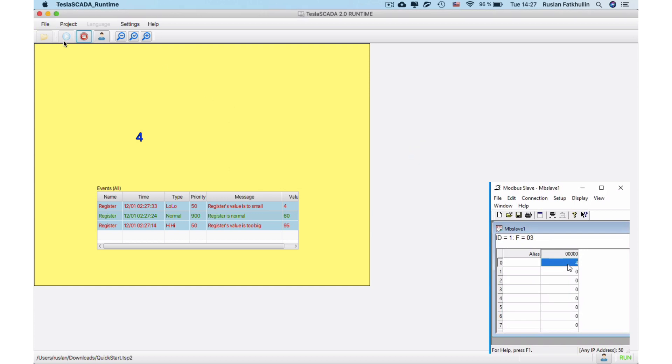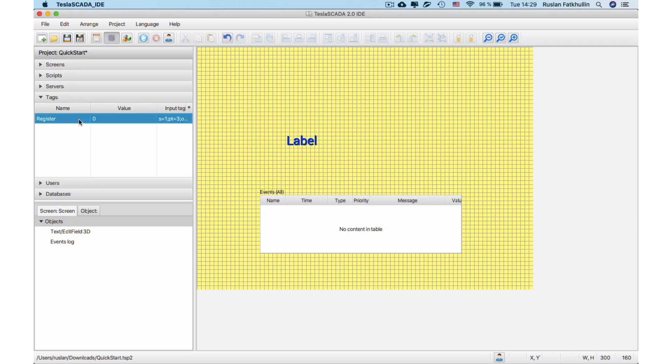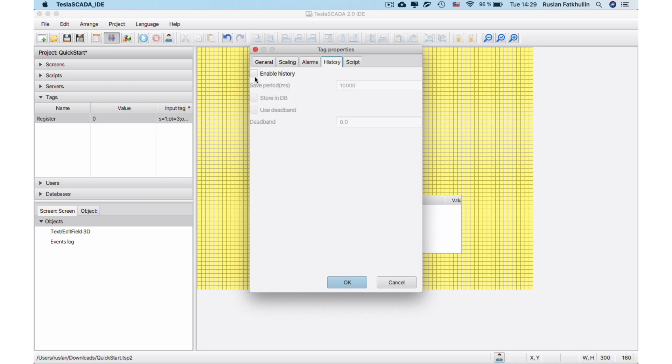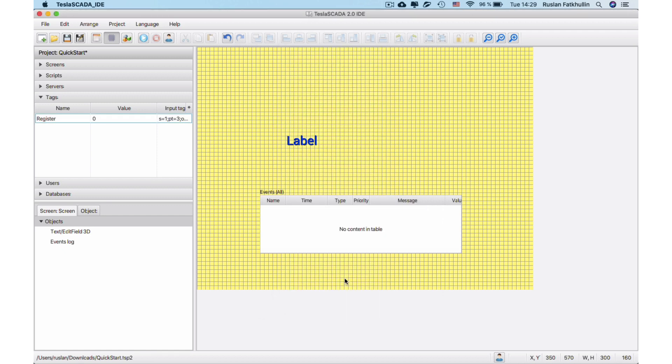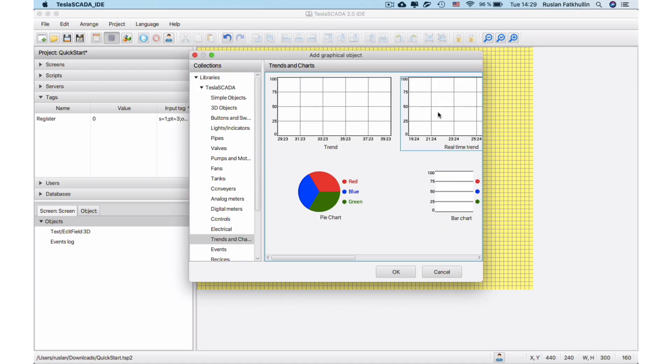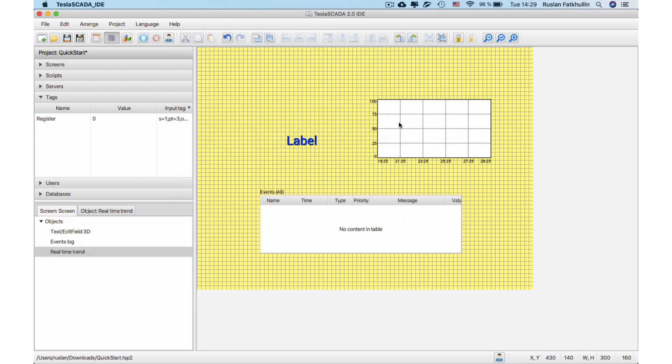And now let's add history logging for our tag in the project. Enable History on the History tab in Tag Properties and change save period to 1 second for better visualization. And let's add real-time trend for visualization tags history data.